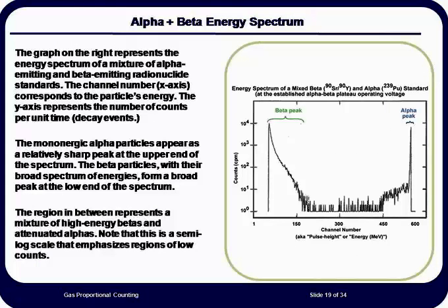A sample containing both strontium-90 and plutonium-239 was counted on a gas proportional counting instrument that had pulse discrimination capability. The spectrum shown here are accumulated counts versus the pulse height. Remember, the pulse height is proportional to the particle energy. Alpha particles in general have higher energies, and thus we expect to find the peak for the alpha particle at the right-hand side of the spectrum.